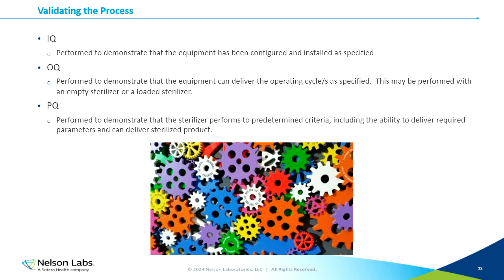The second thing that we need to consider is operational qualification, or OQ. That is performed to demonstrate that the equipment can deliver the operating cycle as specified. This might be performed with an empty chamber. It might be performed with a loaded sterilizer. Depending on your location in the world, there may be test packs that you would use as part of the operational qualification. And then finally, the area where we're going to spend most of our remaining time is performance qualification.